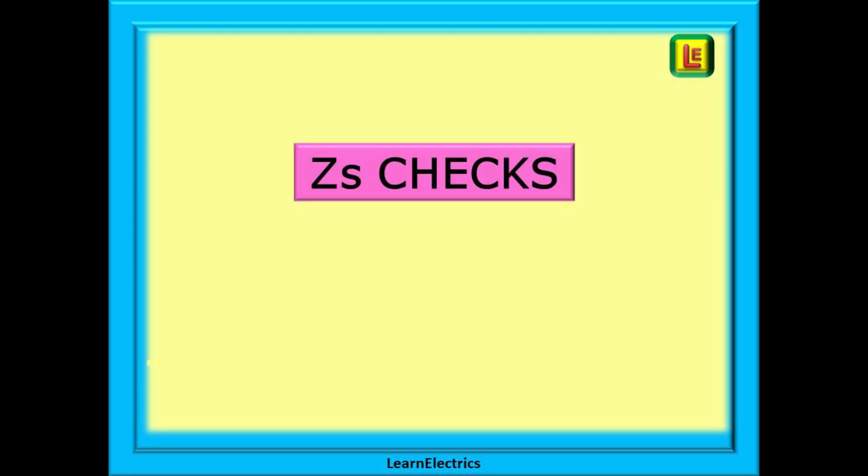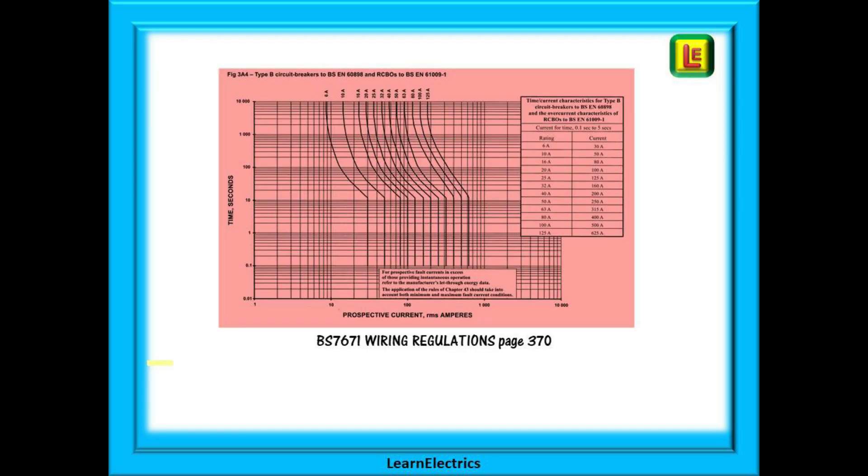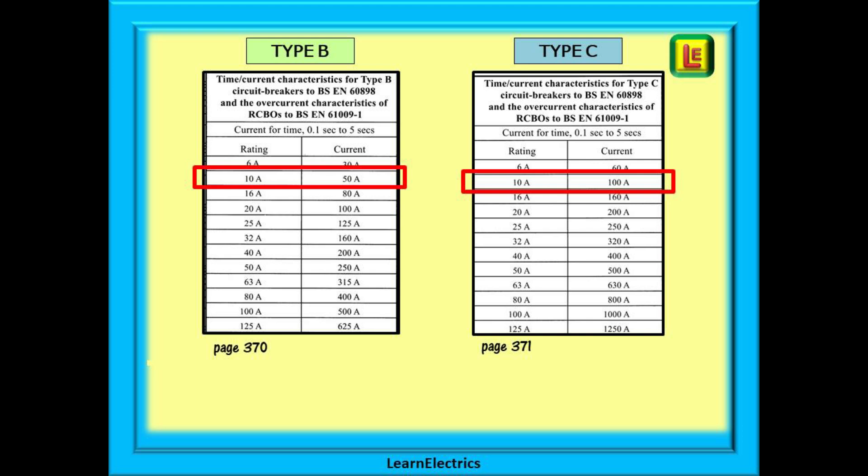Why does ZS matter? How do we know what they should be and what can we do? Here is a page from the wiring regulations book, page 370 in this case. It shows the response curves for a B type MCB. On page 371 are the response curves for a C type and page 372 has the D type curves. We are interested in the table at the top right of each page and we show the tables from pages 370 and 371 here.